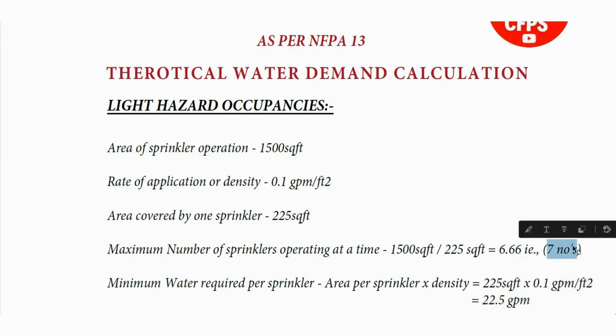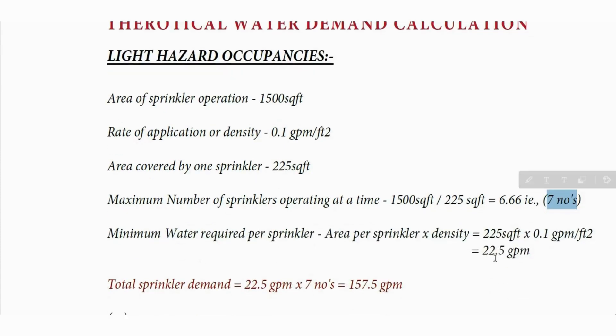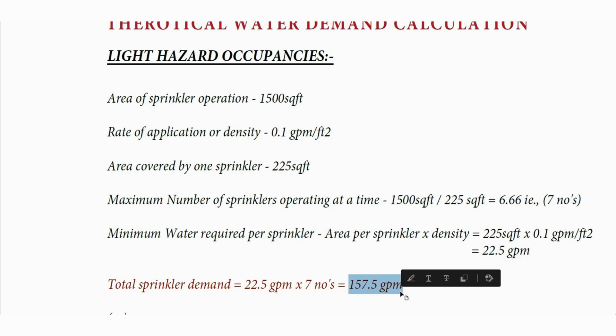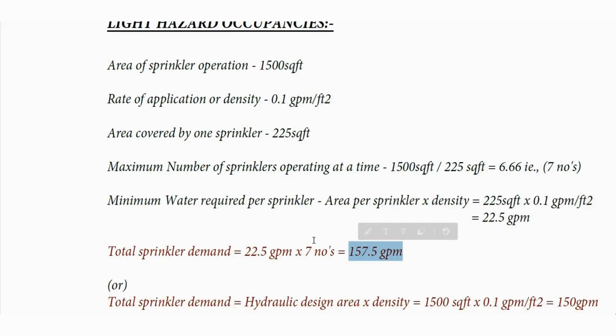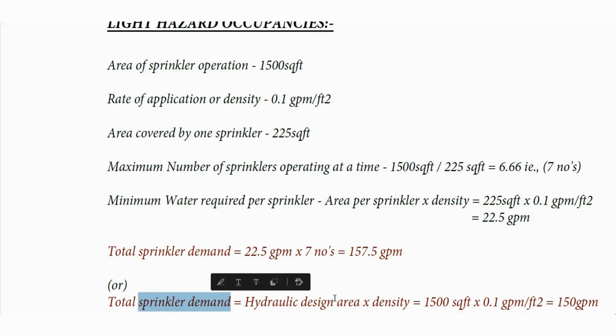With seven sprinklers, we multiply 7 by 22.5 GPM to get the sprinkler demand, which will be 157.5 gallons per minute. There is another way to calculate the sprinkler demand, which I am going to discuss now.